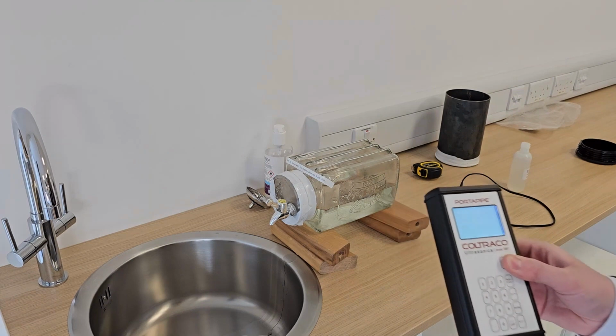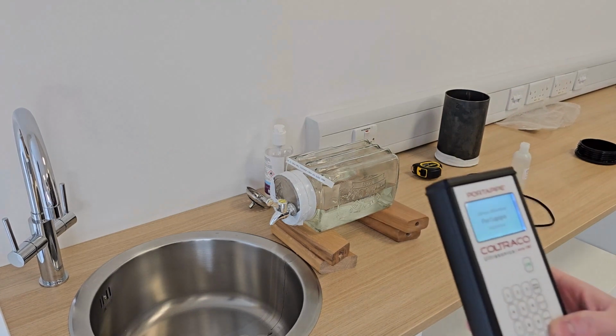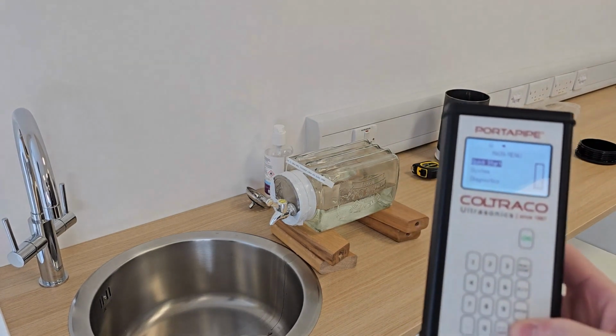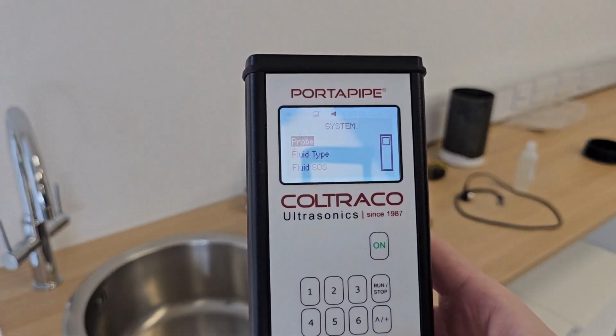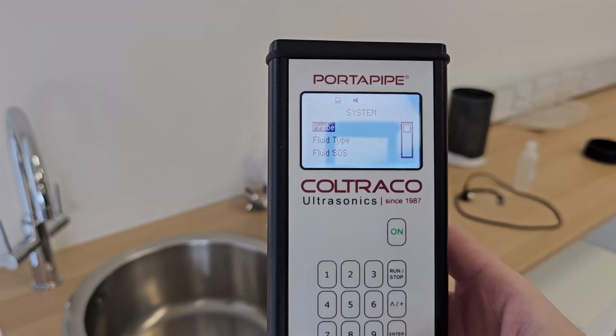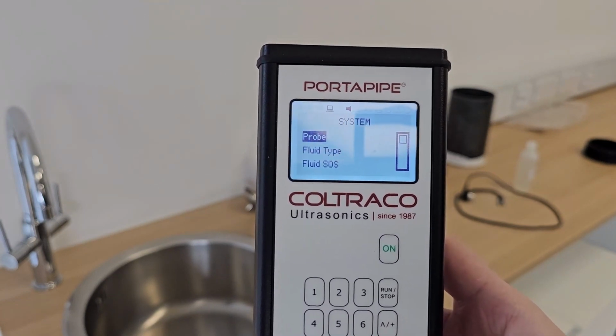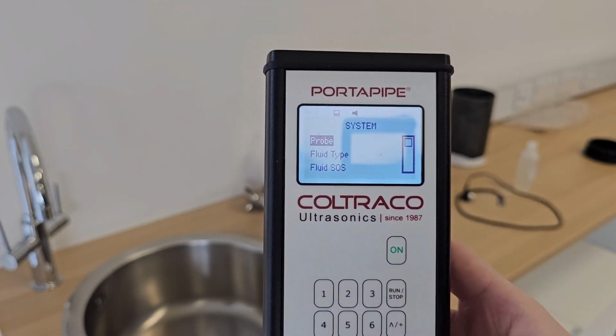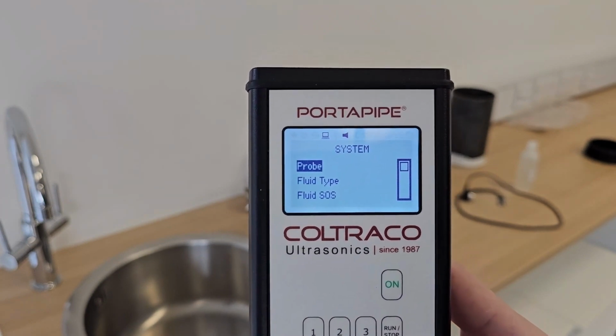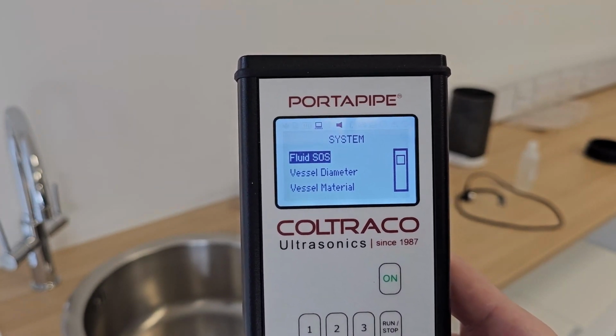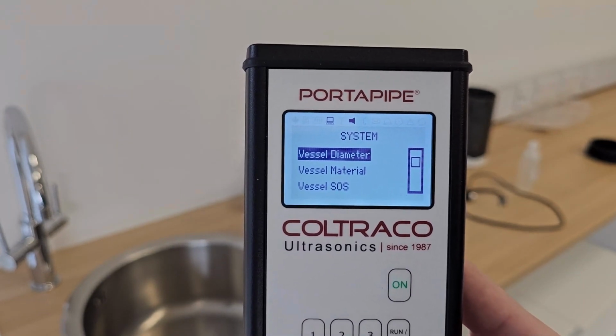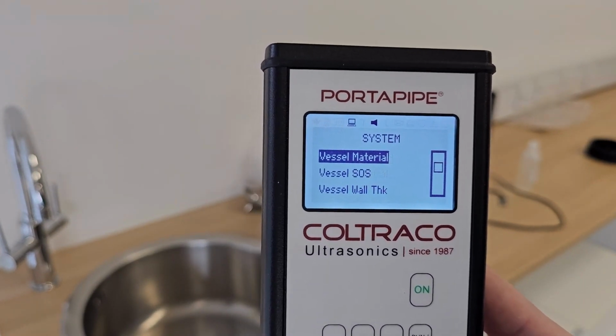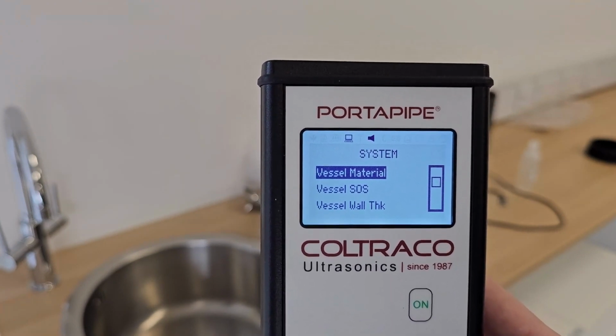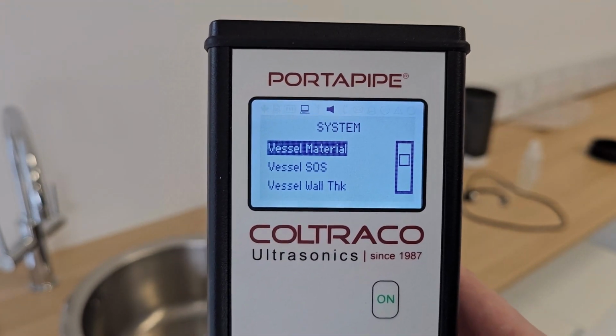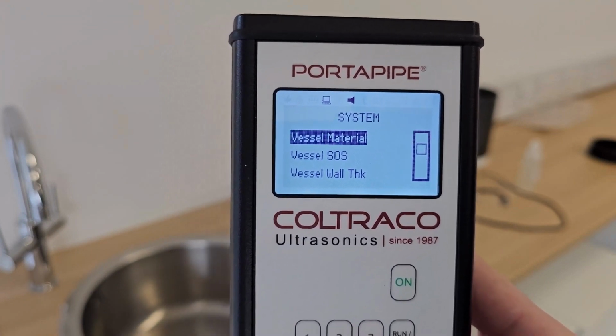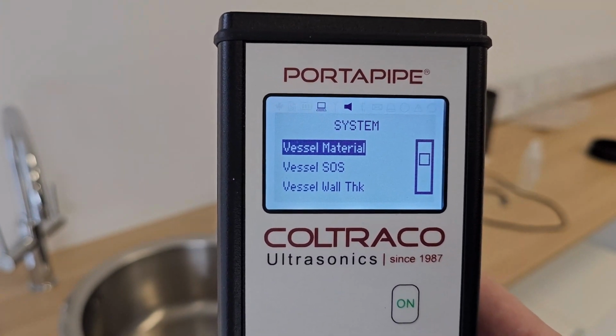So to start with, I'll talk you through some of the settings on the device that might be relevant to your testing. So I'll turn it on, and I'll go down to System, and you see we have a few settings here: probe, fluid type and fluid speed of sound. They won't be relevant right at this stage because we'll be asked to provide those as we start our measurement, so ignore those. Vessel diameter as well we will be asked for as we set up for a measurement. However, vessel material, vessel speed of sound and vessel wall thickness are important if you want to get the most accurate possible results out of your Portapipe, and you'll have to go into the settings to change those manually.